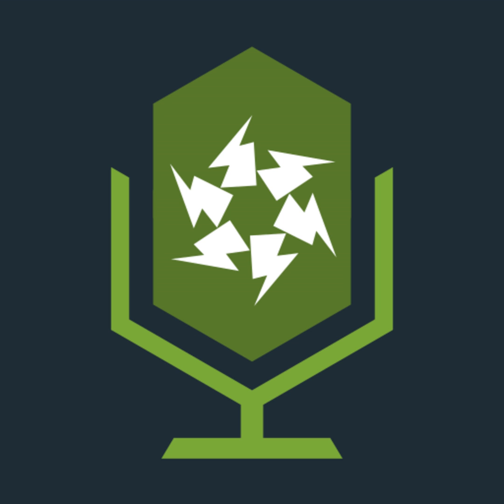Now, while I tie this in, just have a think. What if this is a twin and earth cable? Surely the earth has already been determined. You know, 10 mil. What's the size of an earth in 10 mil? Is it 4 mil, 6 mil? Depends what you think. 4 mil is what I have, and I use in the book. So if this calculation says I need 5 mil, or I need 7 mil, then I'm in trouble. But I want a number under 4 when I do this.